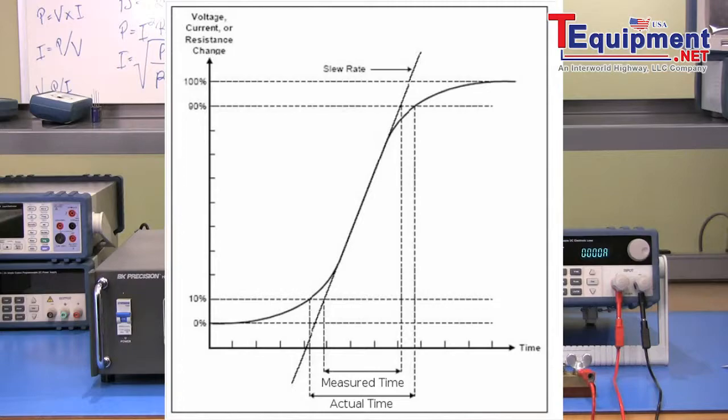Hence, the slew rate calculation is simply the difference in the load change, in this case rated max current minus 0 amp, all over T, where T is the measured time from 10% to 90% region, and rated max current is the specified maximum current of the load under test.